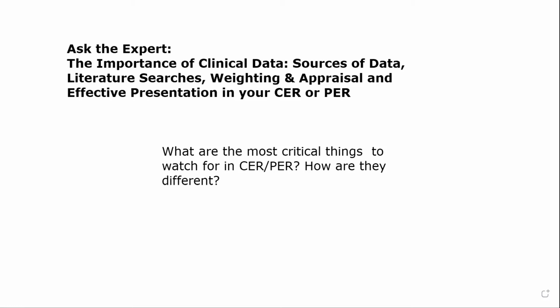And that is where you're setting the safety and performance objectives and the acceptance criteria by which your subject device's data will then be measured to answer this question: is your device safe and does it perform as intended within the state-of-the-art landscape? The state-of-the-art section of the CER and PER sets your device up to be a part of a state-of-the-art milieu within its competitors. So that's where you start that story.